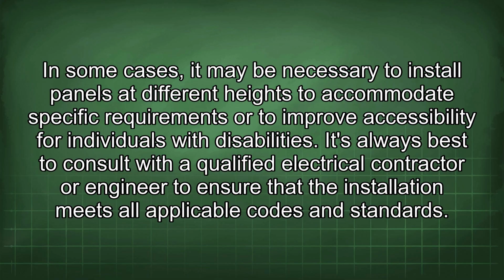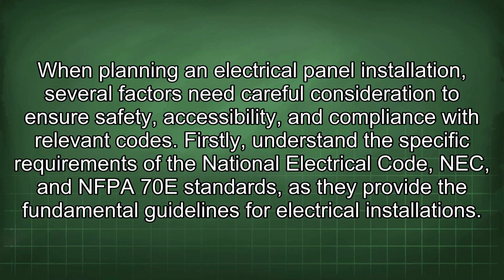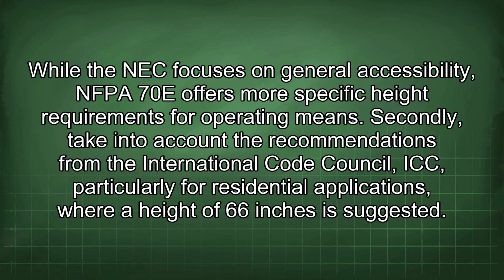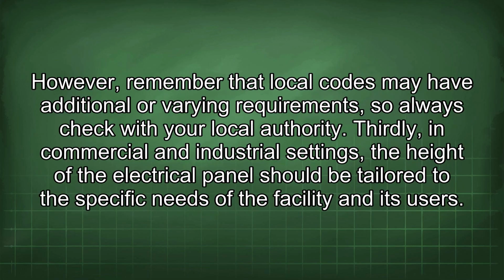codes and standards. When planning an electrical panel installation, several factors need careful consideration to ensure safety, accessibility, and compliance with relevant codes. Firstly, understand the specific requirements of the National Electrical Code, NEC, and NFPA 70E standards, as they provide the fundamental guidelines for electrical installations. While the NEC focuses on general accessibility, NFPA 70E offers more specific height requirements for operating means. Secondly, take into account the recommendations from the International Code Council (ICC), particularly for residential applications where a height of 66 inches is suggested.